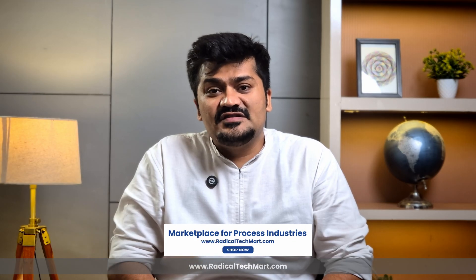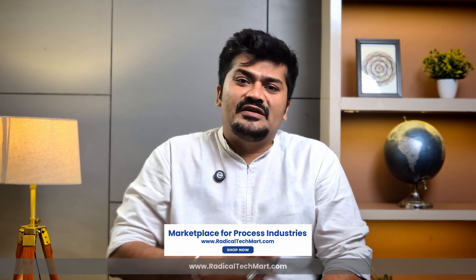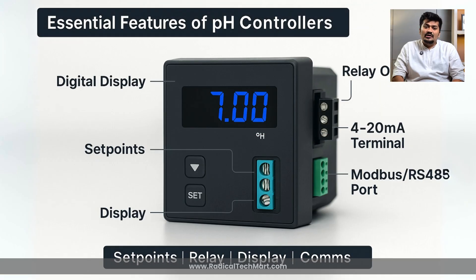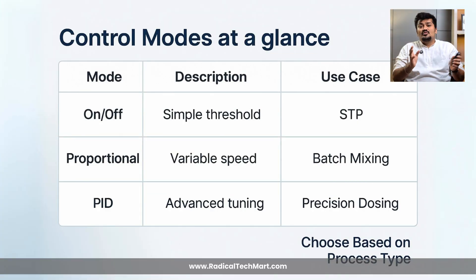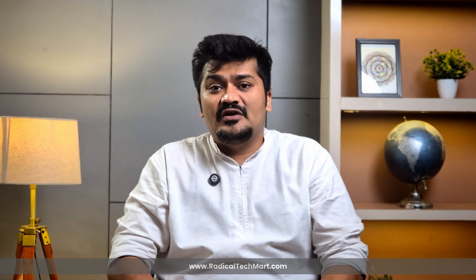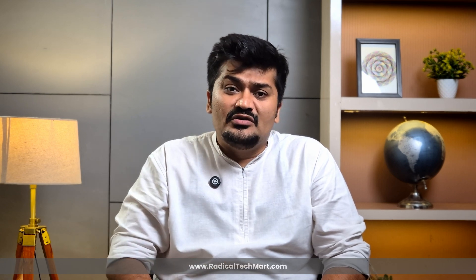Now let's cover key features and outputs. A good pH controller includes standard features like: setpoint configuration with upper and lower pH limits; relay outputs to control pumps, valves and buzzers; a digital display showing real-time pH reading; control modes like on/off, proportional or PID; and analog output options like 4-20 mA, Modbus or RS485 for PLC or SCADA integration. Quick tip: always check if the controller has a manual override mode, which is useful during maintenance or calibration.